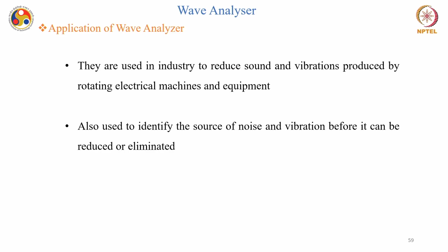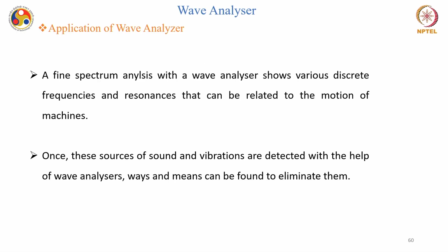They are used in industry to record sound and vibrations produced by rotating electrical machines and other heavy equipment. Also, they are used to identify the source of noise and vibration before it can be reduced or eliminated. A fine spectrum analysis with a wave analyzer shows various discrete frequencies and resonances that can be related to the motion of machines or different parts of the machines.